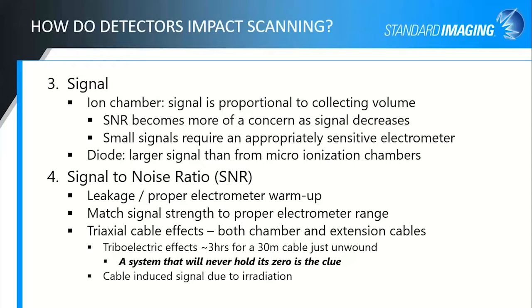And so that's something just to consider. We think about it a lot when we're doing our calibrations. We don't necessarily think about it as much as maybe we should with the scanning tanks, because the small signals that you get from these small ionization chambers do require an appropriately sensitive electrometer. With a diode, you do get a larger signal than from micro-ionization chambers, so the low end of that signal range on your electrometer is a little bit less critical. Also, if you're looking at those electrometers, make sure you're looking primarily at the current and not just the charge that you would collect over whatever length of time, although both are critical.